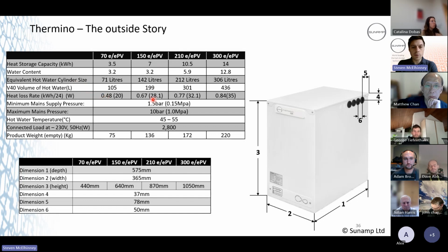So your 70, your 150, your 210, your 300. And what we can do is compare them to a cylinder on the next slide. So 0.48 kilowatt hours over a 24-hour period for a 70. What customers ask us is, how long is my capacity going to last if I go away on holiday or whatever? So you take the kilowatt hours for that unit, 3.5 in this case, and divide it by your 0.48. That gives you the length of time in days from 100% charged to 0% depleted.